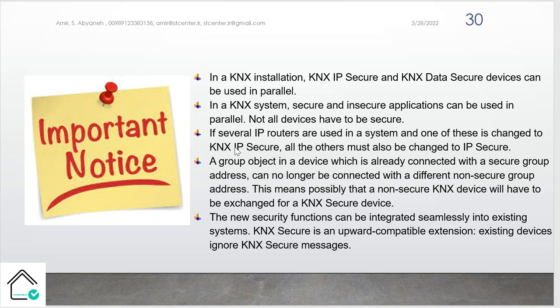A group object in a device which is already connected with the secure group addresses can no longer be connected with different non-secure group addresses. This means possibly that a non-secure KNX device will have to be exchanged for KNX Secure devices. The new security functions can be integrated seamlessly into existing systems. KNX Secure is an upward compatible extension. Existing devices ignore KNX Secure messages. So it's upward compatibility. You can use it in old projects also, but you should follow the rules.